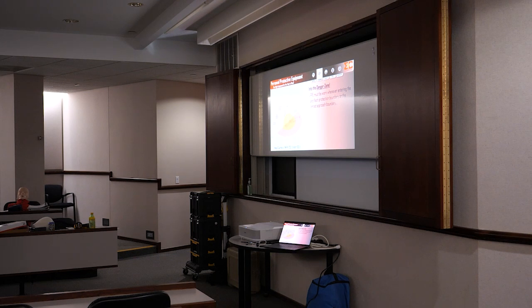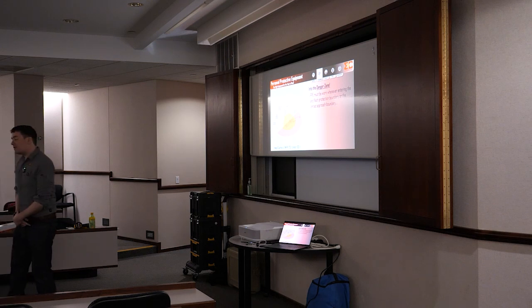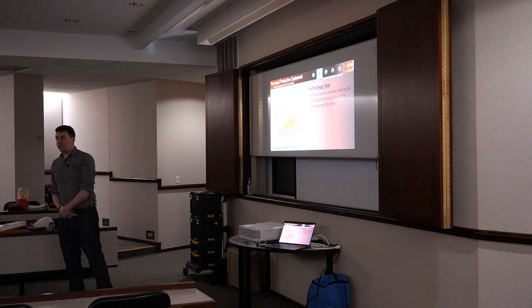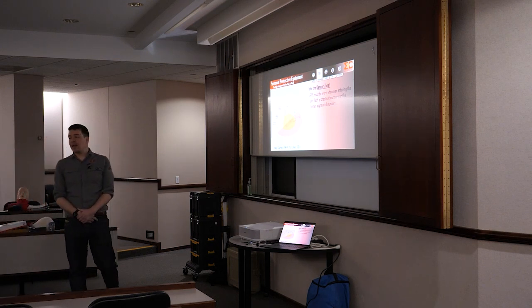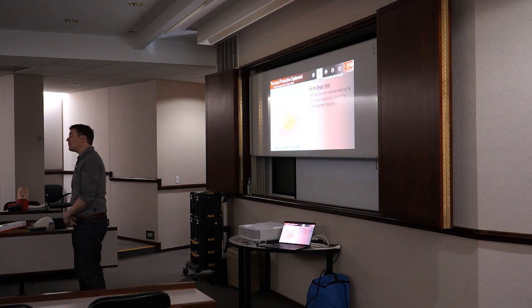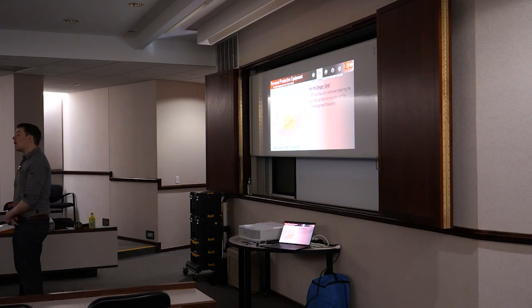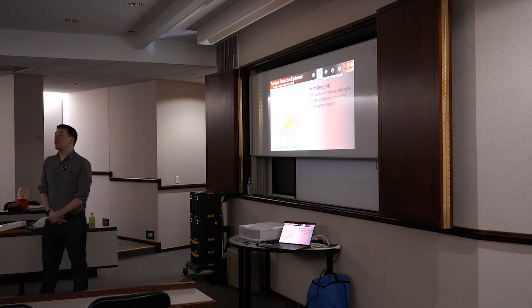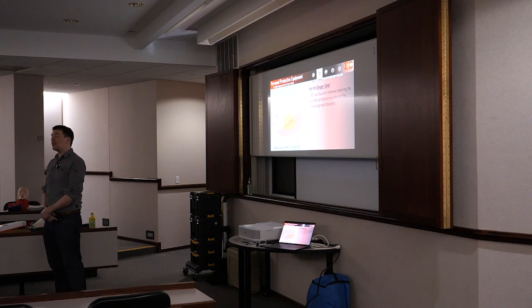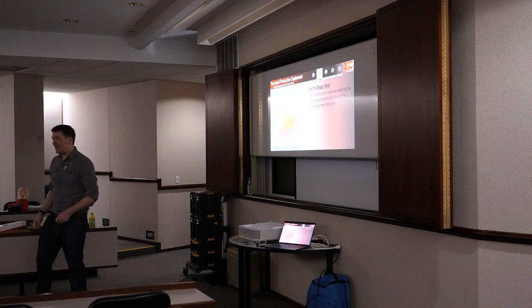The steel-toe shoes, do they have to be electrically rated? They have to be electrically rated. So they do not necessarily have to be steel toe - they can be composite toe, which is becoming a very popular option because composite toe is very light. However, they still have to carry an EH rating, an electrical hazard rating, stamped either on the insole or on the heel.